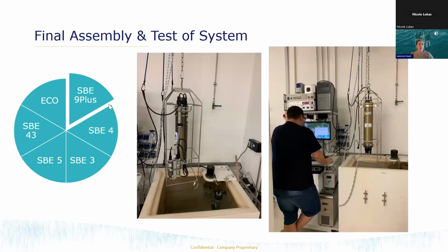So here's an example: you've got the 9 Plus. It took its own path through service and calibration, but this particular one was also equipped with an ECO sensor, an SBE 43 oxygen sensor, temperature, conductivity, and a pump. It's important that after those services have been performed, everything gets put back together, and then we do a final test, a dynamic check that the integrated system performs exactly the way it should.